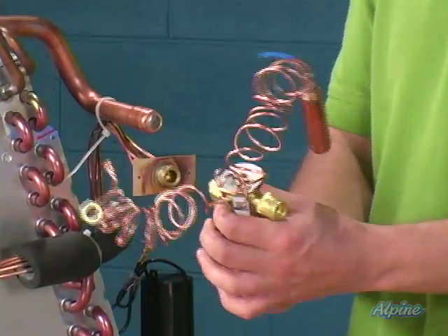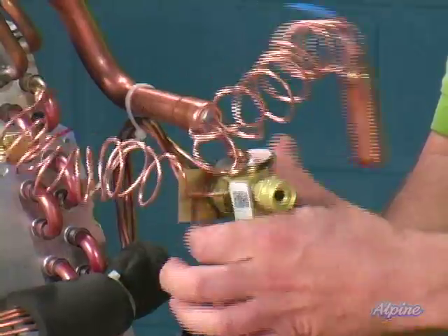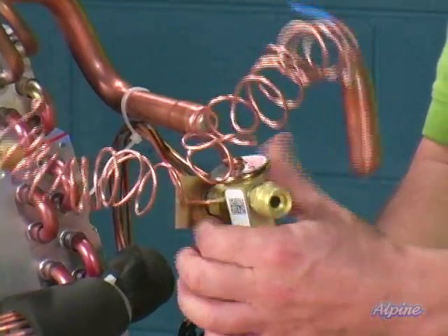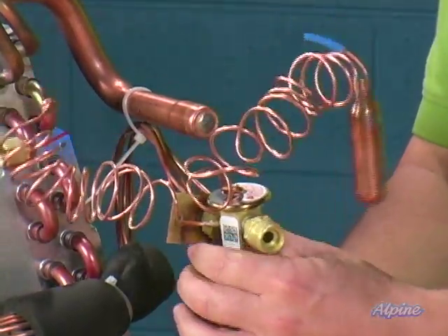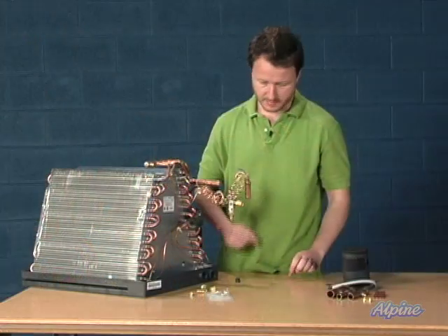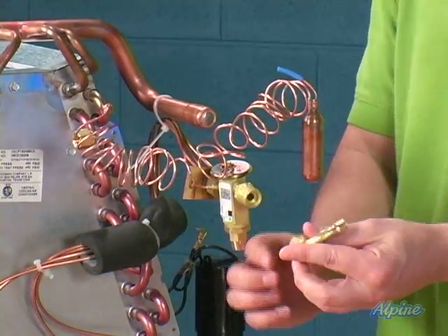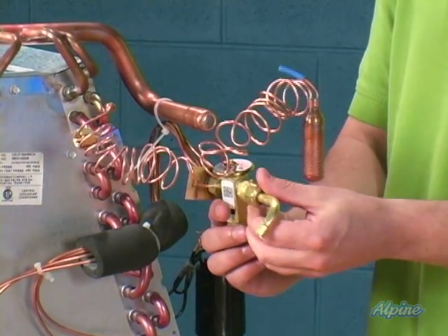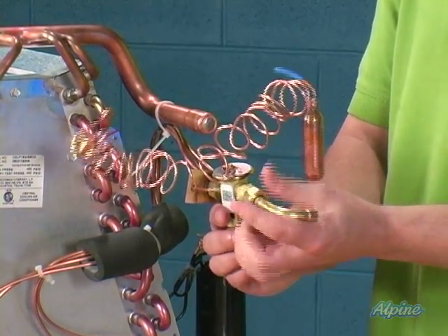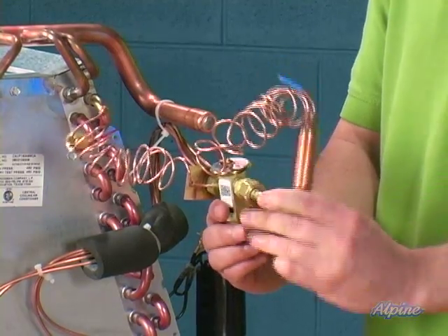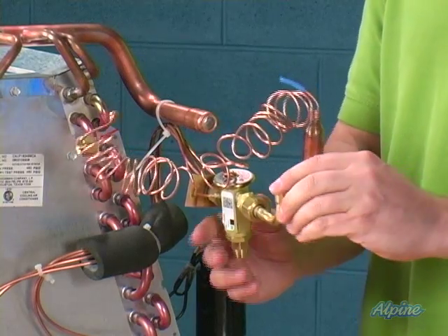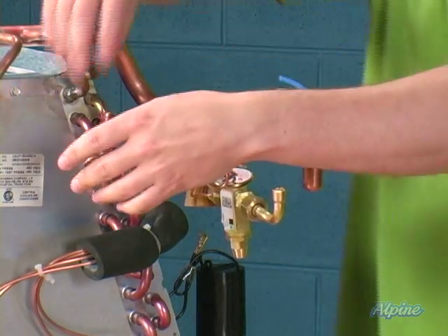So here's how it goes. Real simple to do, actually. Because it has these flare fittings, it screws in place. So I'm just tightening this nut on here first. Once I've got that in place, then I take this little piece, which was included with the coil, and this flare nut, put it on the other end. This is where I'll solder in the liquid line, that small line set. It takes care of that part.